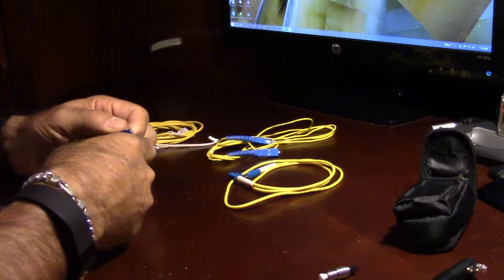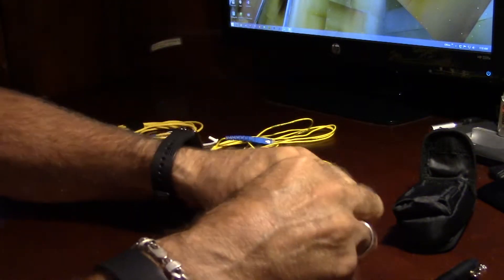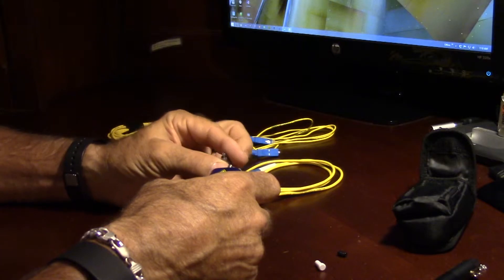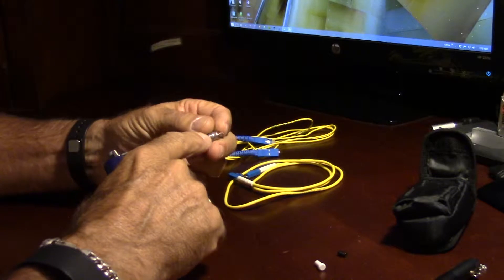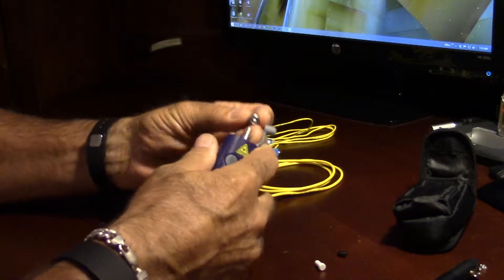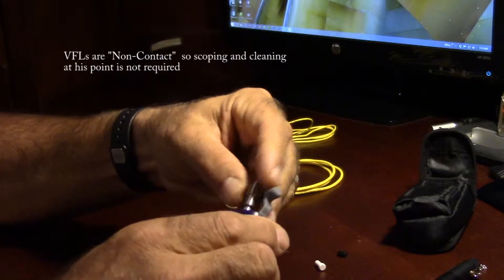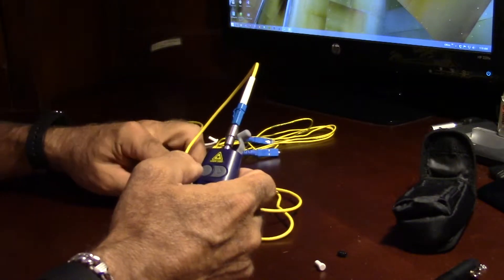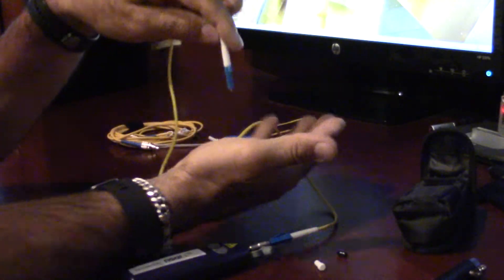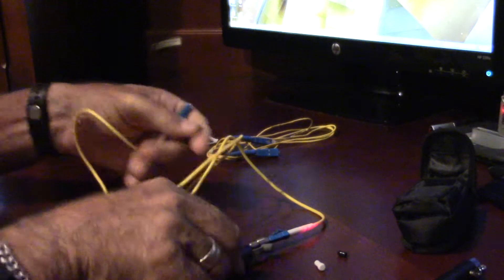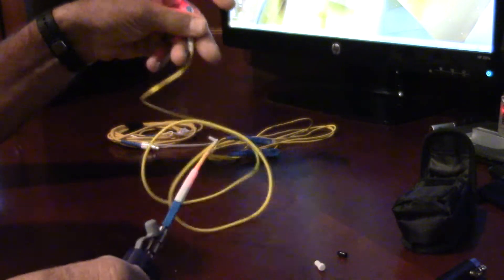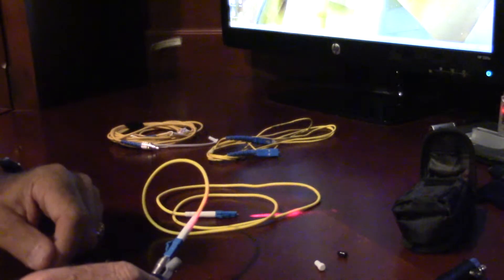So we'll just start with the LC. They're used for fiber identification, for fault finding, etc. For the LC's we have to use a little adapter. These are not adapters for utilizing or changing LC to SC or the 1.25 to 2.5. You can't use these in an OTDR or a power meter. There's a lot of loss across these. So you just plug in the 2.5 into your visual fault locator, plug in your 1.25 millimeter. We turn this on and I'm going to turn this light out. This is flashing right now. Let's get it on a constant. So this shows us in this jumper that it's a fairly good condition jumper. There's not macro bends in it. We're going from A to B. Everything looks good on this one.